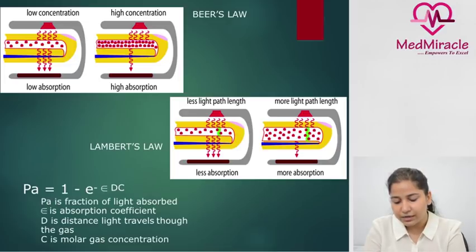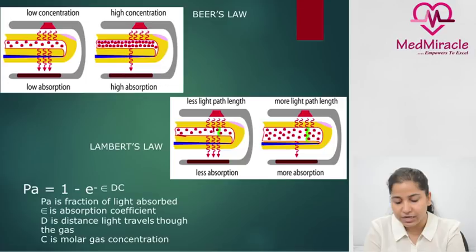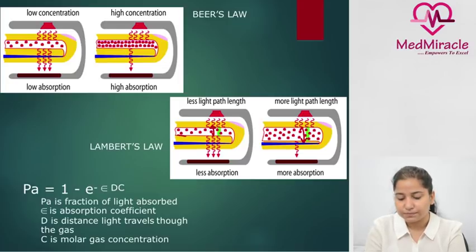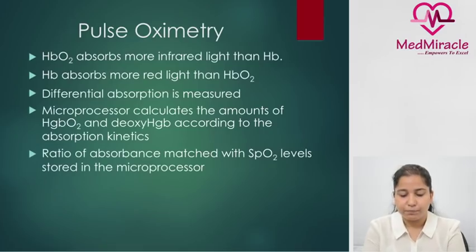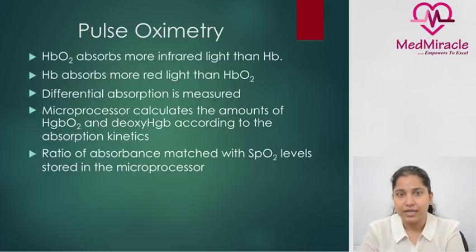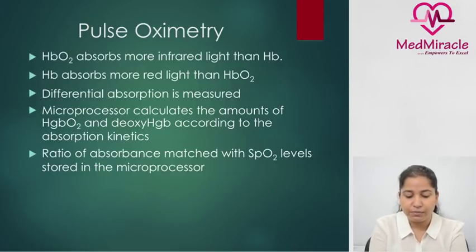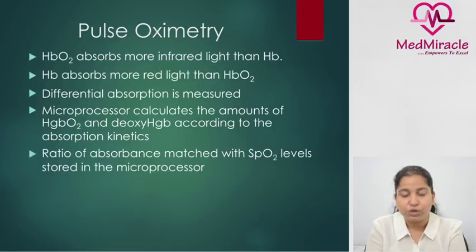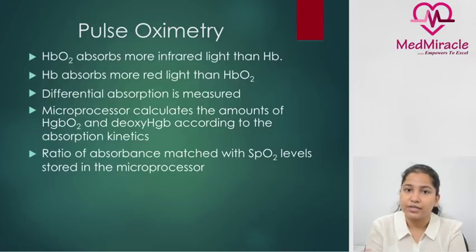As seen in the diagram, with vasoconstriction the path followed is less, so there is less absorption. With vasodilation, the path increases and there is more absorption. Oxyhemoglobin absorbs more infrared light than hemoglobin. Remember: oxyhemoglobin absorbs more infrared light and hemoglobin absorbs more red light.